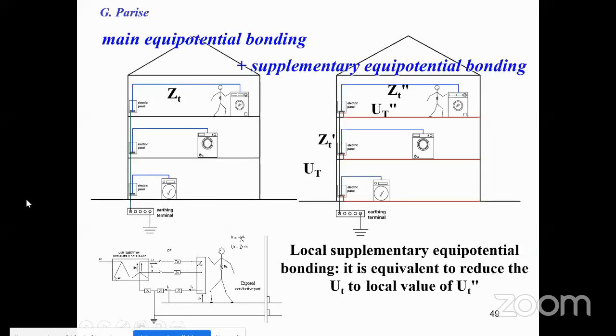So let me show how. If I have a washing machine connected to the ground, and there is no supplementary equipotential bonding, you can see that this connection goes directly to the earthing terminal of the local ground electrode.